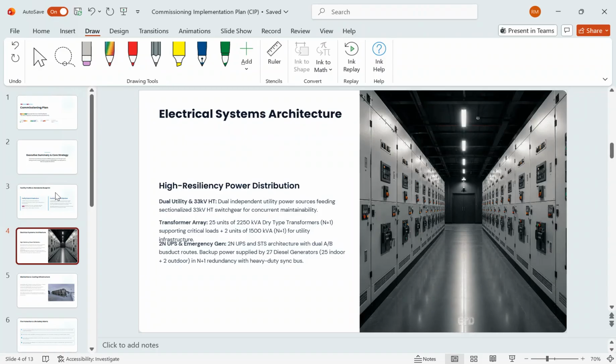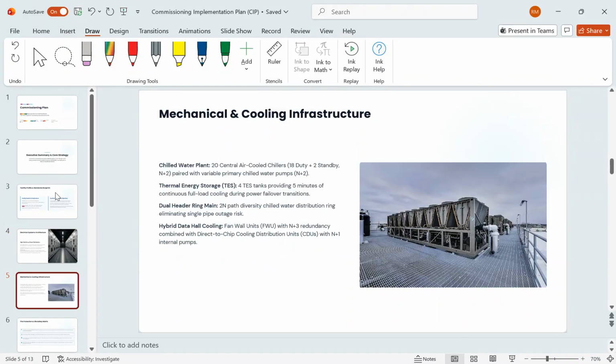It is provided to you at the tender stage, the detailed BOQ of what we have to commission, along with the data set. In the data set, there will be an overview of the facility. It is already provided. Again, it has mechanical, ELV, security, and BMS. Let's quickly glance through them. Coming to mechanical and cooling infrastructure, the chilled water plant has 20 air cooled chillers, where 18 are duty and 2 standby, paired with N plus 2 configured chilled water pumps. It has 4 thermal storage tanks which provide 5 minutes of continuous cooling in case of power failure during transitions and so on.